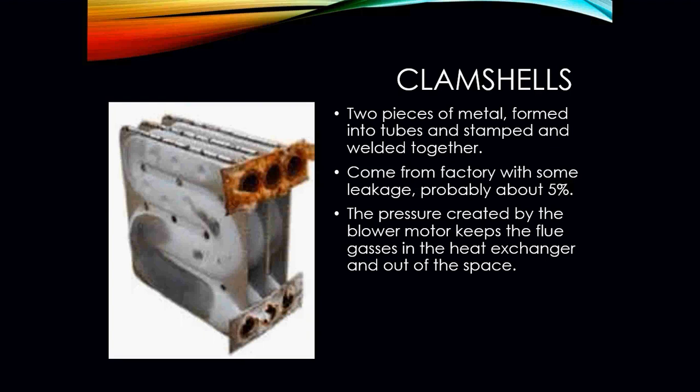One of the biggest problems with these heat exchangers is that if we over-fired the furnace, they failed relatively quickly. You can see in this picture some of the damage that can occur from an over-fired heat exchanger. If you look at this particular area, you can see the discoloration — that is a sign of heat stress. That heat exchanger was being over-fired, meaning the flame was too large, reaching around and looping, over-firing that piece of equipment.